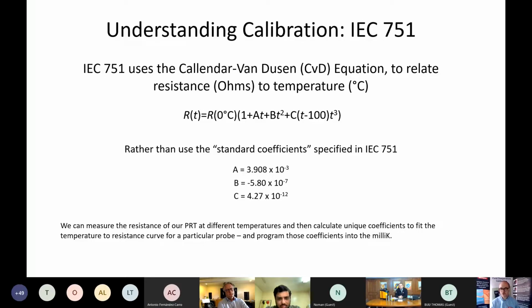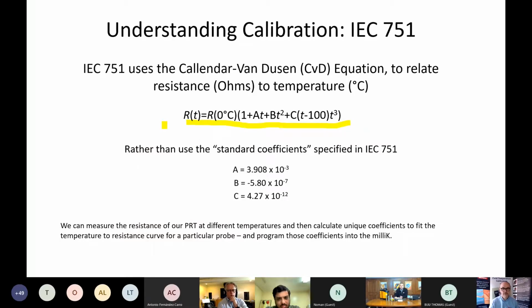So how do we calibrate them? Well, we could use IEC 751. That's the method used in the standard, the Callendar-Van Dusen (CVD) equation specified in IEC 751. And this is the equation here. Let me just put my pointer on. This is the equation here in the standard, and the standard gives us the tolerances, and that's how it works. But what we can do, we can measure the PRT at different temperatures. We can calculate unique coefficients to fit the temperature resistance curve for a particular probe, and then we can program those coefficients into the milliK.